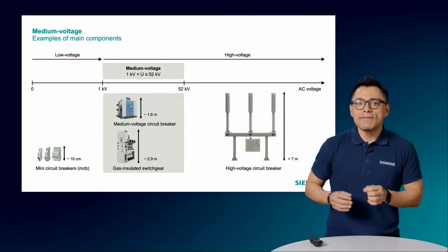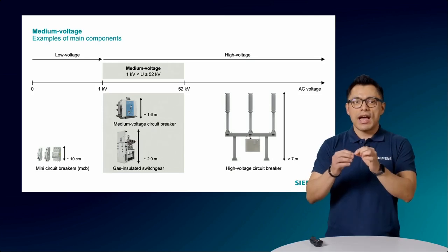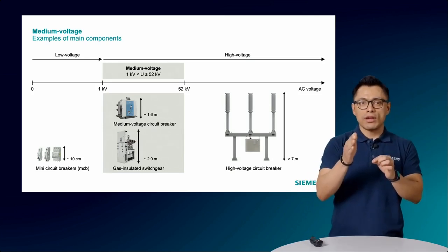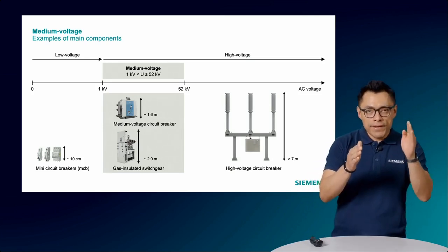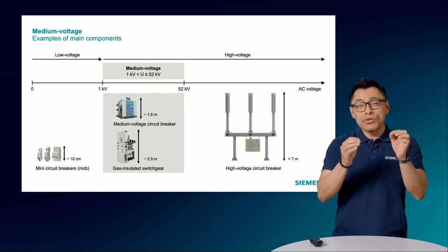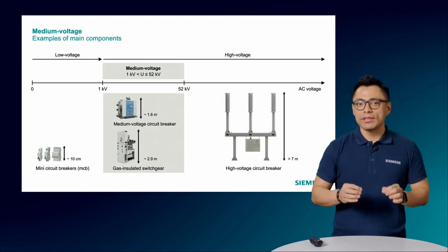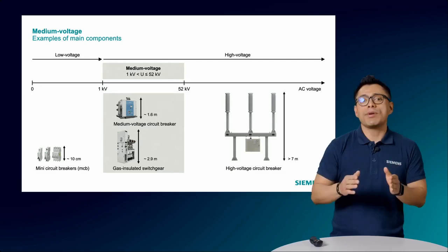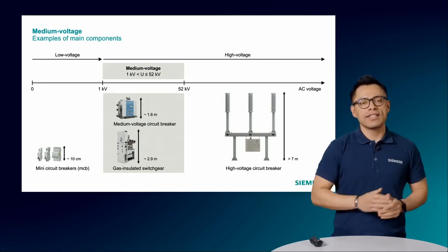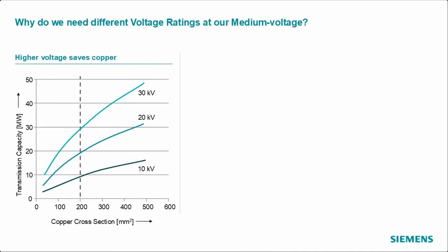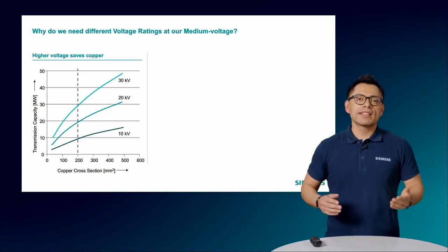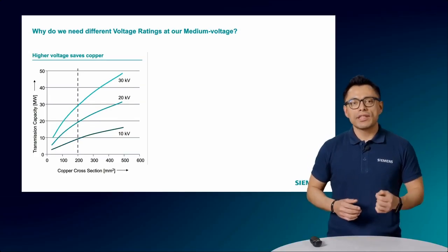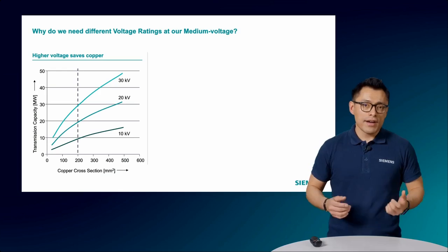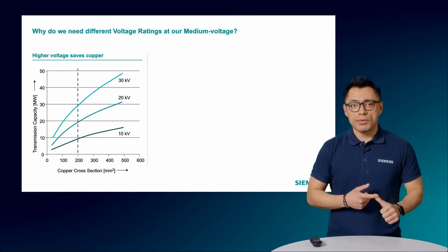Medium voltage is defined as the range above 1 kilovolt up to and including 52 kilovolts. It is really a sub-range of high voltage that serves as a bridge between low and high voltage systems. It's very relevant to distinguish between different voltage ratings in medium voltage. There are several reasons for using different voltage ratings. Some reasons are efficiency in power distribution.